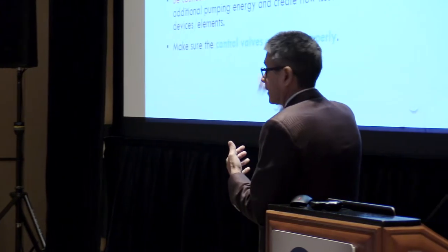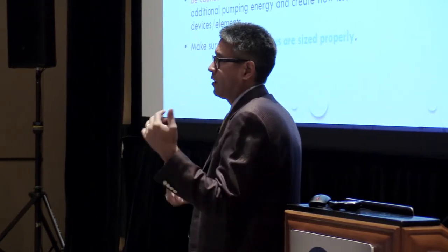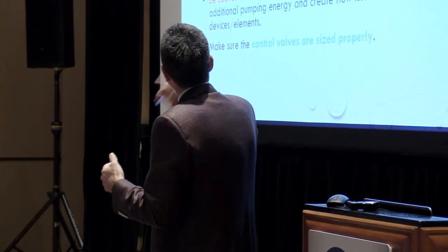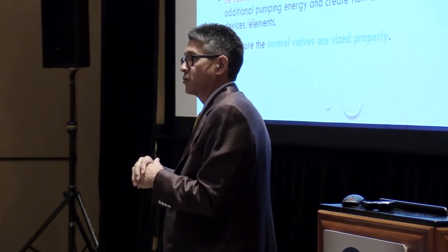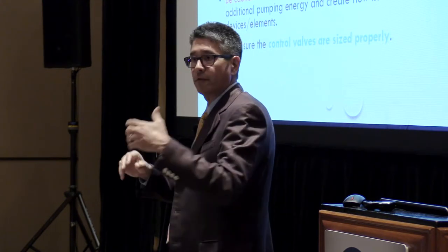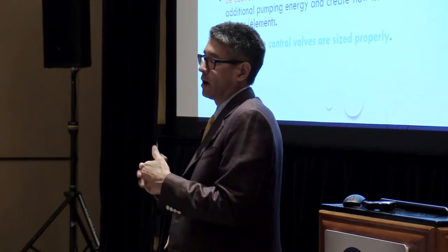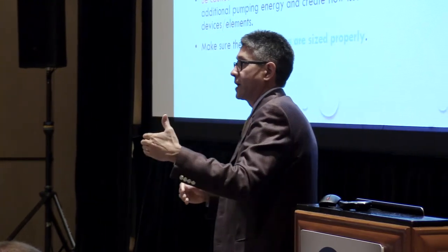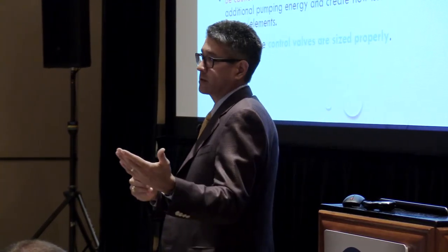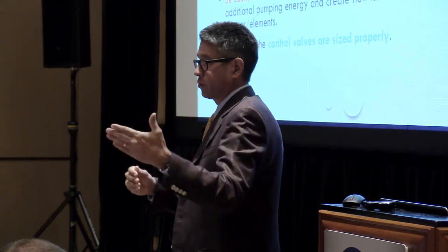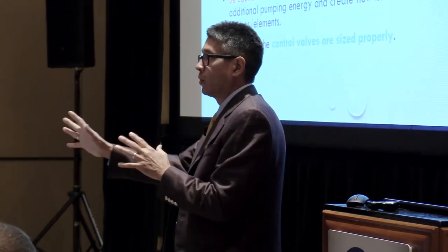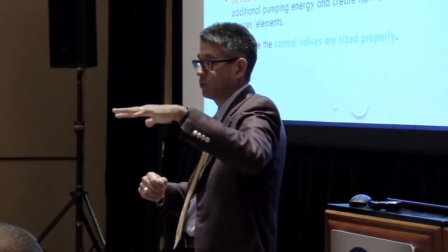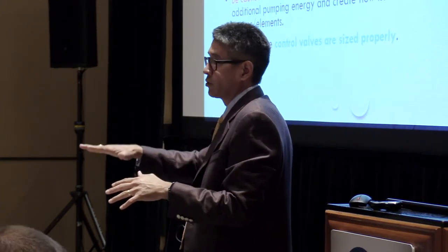So the big thing I had mentioned earlier, if you can get involved early and you can sit down and start looking and saying, hey, I can get some branch balancing valves put in certain places, whether it's off to each floor or off to each building or off to a wing or something like that. In a lot of scenarios, you can work with that branch balancing valve, set that for a total flow out to that wing, and know what you got, and then that way you might not have to proportion as much throughout the rest of the wing, but you can proportion your major branches.